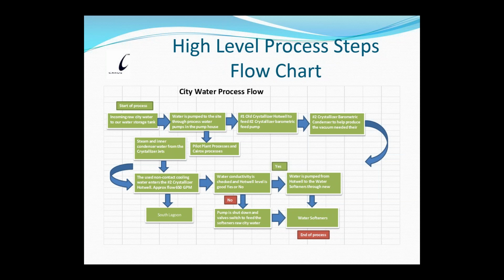The other place that it goes is to the #1 old crystallizer hot well to feed the #2 crystallizer barometric feed pump. That barometric feed pump pumps to the, well, as you can see, the #2 crystallizer barometric condenser. It pumps there to help produce the vacuum needed there. Right here, as we come across, we come to this point. This used non-contact cooling water enters the #2 crystallizer hot well. Approximate flow is 650 gallons a minute. What goes into that is steam and intercondenser water for the crystallizer jets. And what comes out, that water at 650 gallons a minute just goes to the South Lagoon. A South Lagoon is a holding pond before it gets discharged into the Little Vermilion River.